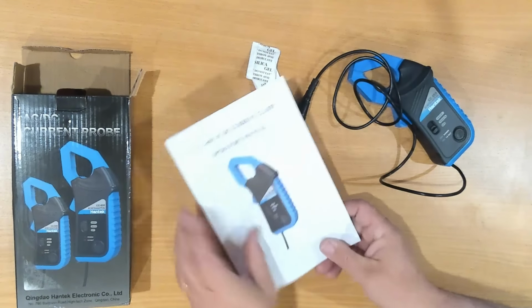The output going to this is in millivolts per amp. So on one range it's 1 millivolt per amp, on the other range it's 10 millivolts per amp, so you can get a stronger signal. It'll go round a 30mm diameter wire maximum. It's got a green light to say when it's turned on and a red light to indicate when the battery needs to be replaced. It does run on a 9-volt battery, and there's a screw that when you loosen it off lets you slide the cover out to gain access to that 9-volt battery.